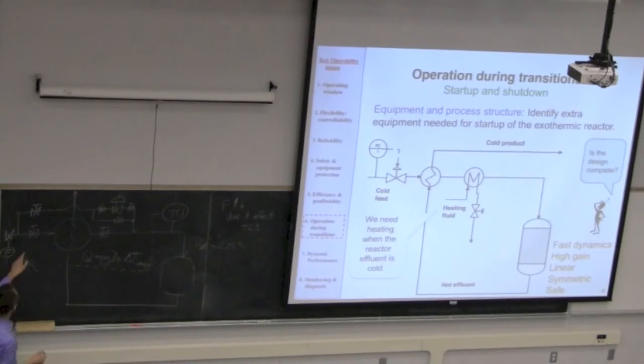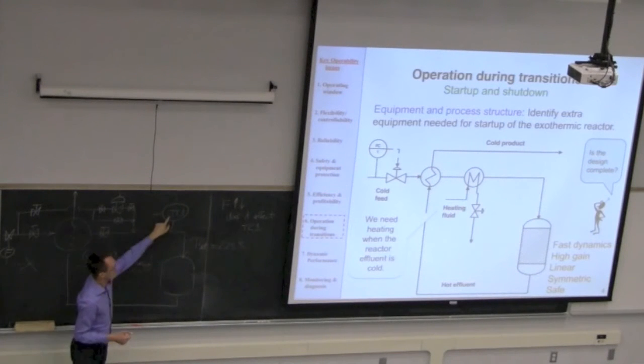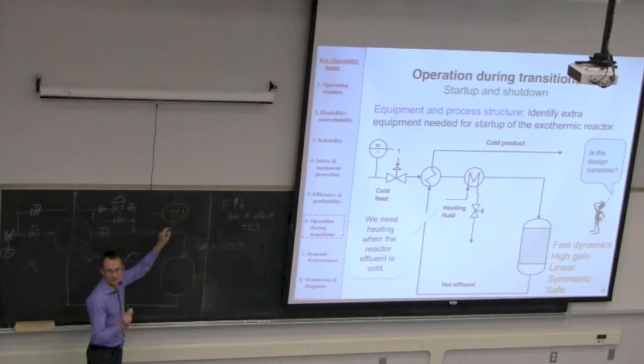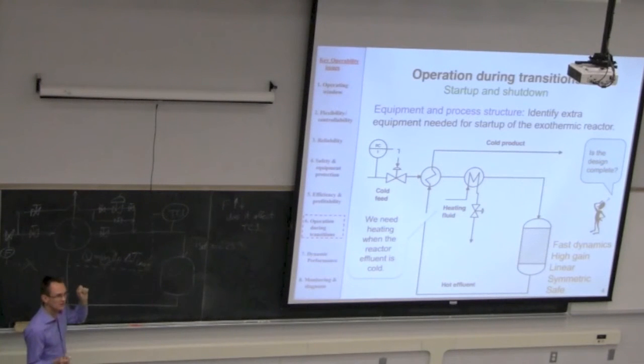So we looked at this thing as an alternative yesterday, or we proposed this loop, where we're saying let's open and close this valve over here to affect this temperature. Cause and effect relationship between that valve position and the temperature? Yes, absolutely. Does it have fast dynamics? If I open the valve, how long is it going to be before I see a change over here? That's what dynamics refers to. Fast dynamics, slow dynamics. Extremely fast dynamics. You open that valve almost instantaneously, you'll see a change in that temperature. Fluid typically flows in pipes around 10 meters per second if it's liquid. Vapor phase, 30 meters per second. It's a very quick change in that valve position to seeing a change in temperature.